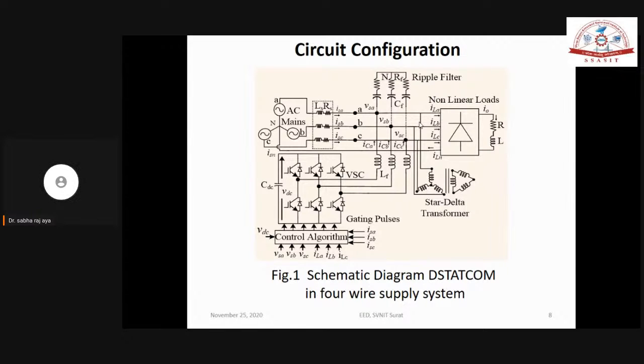So what type of conclusion do we get? Using this filter, we have just shifted the harmonics from current to voltage. That is also one conclusion. We always say that we have compensated harmonics, but on the other side, people have also drawn another conclusion: we have not compensated, we have just shifted. If we look at the data I told, before compensation 4% in voltage, 21% in current.